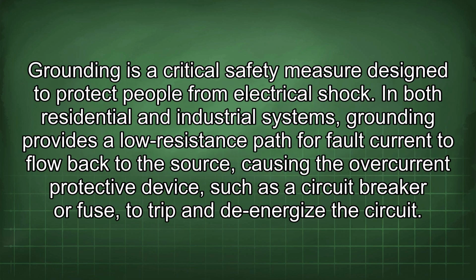Grounding is a critical safety measure designed to protect people from electrical shock. In both residential and industrial systems, grounding provides a low resistance path for fault current to flow back to the source, causing the overcurrent protective device, such as a circuit breaker or fuse, to trip and de-energize the circuit.